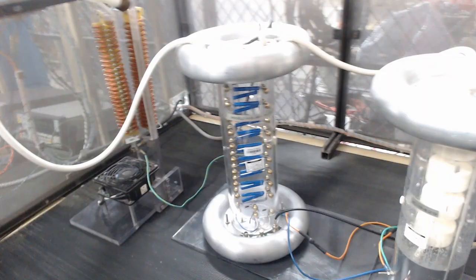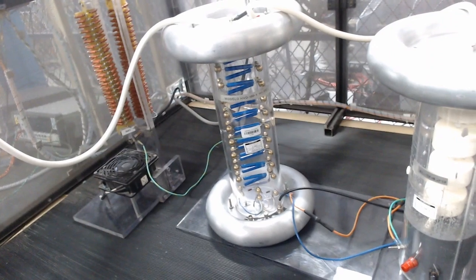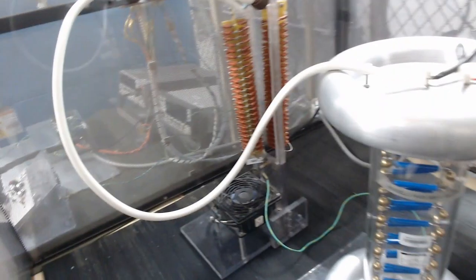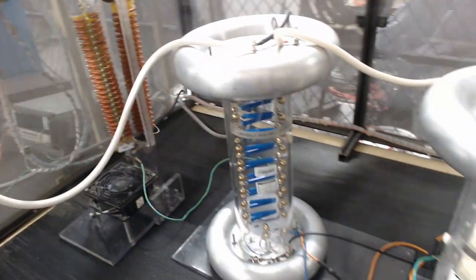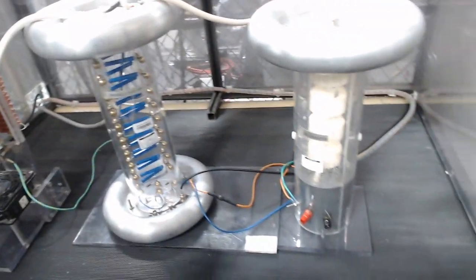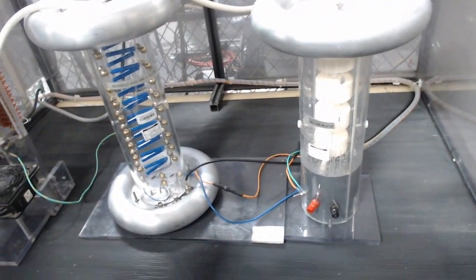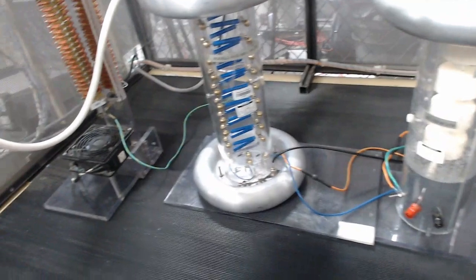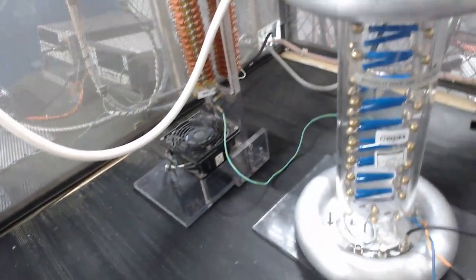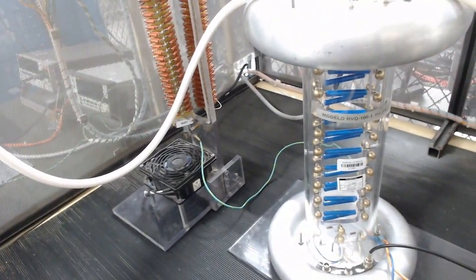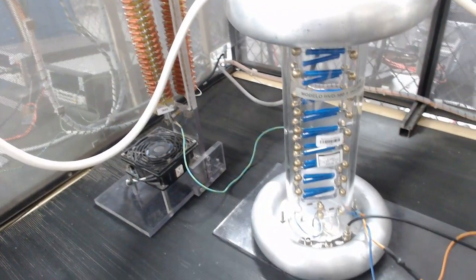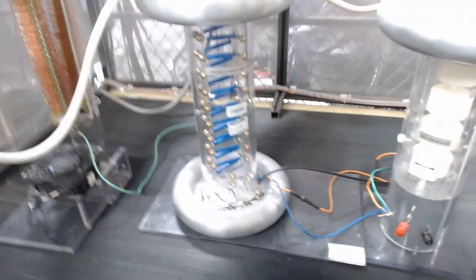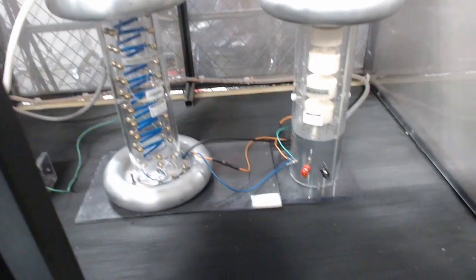Here you'll be able to have a closer look at the high voltage test setup. Ripple checker and high voltage divider are calibrated instruments. You will also notice that the current return path of the high voltage divider and the load are tied together, and the sum of those currents is measured at the current meter.